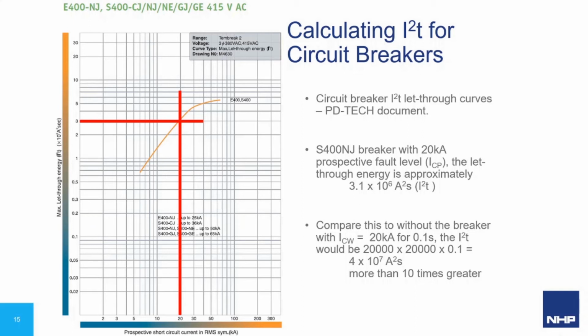For example, an S400NJ breaker seeing a 415 volt fault with a 20 kA prospective fault current. The integral energy that would be let through the breaker is approximately 3.1 times 10 to the 6, as can be shown on the table on your screen. If we compare this to the fault available without the breaker acting at 20 kA for, let's say, 0.1 of a second, the energy integral would be 4 times 10 to the 7. This is more than 10 times greater.